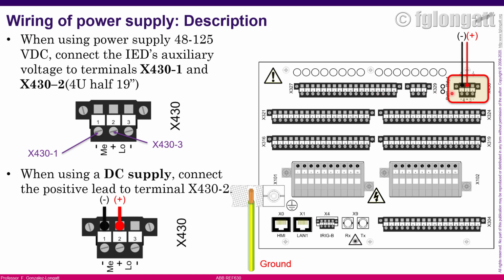To repeat: in this specific IED, the 4 rack unit, 19 inches, we use this three-terminal connector, the X430. It is used for the power supply, or auxiliary voltage supply, to the relay. Specifically, we need to take into account terminals X430-1 and X430-2, because those terminals define the place where we connect the cable from the DC supply.